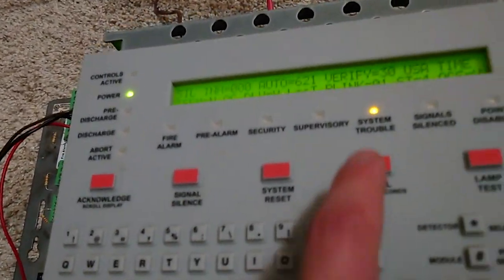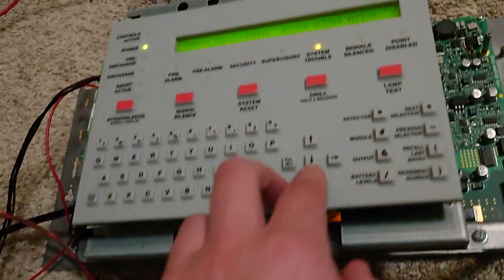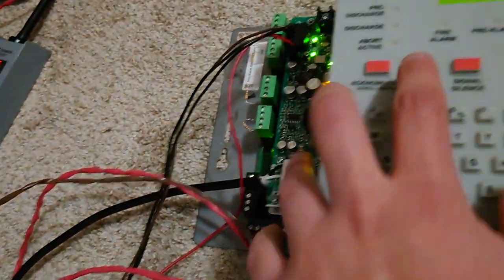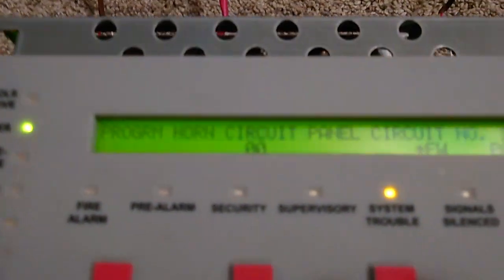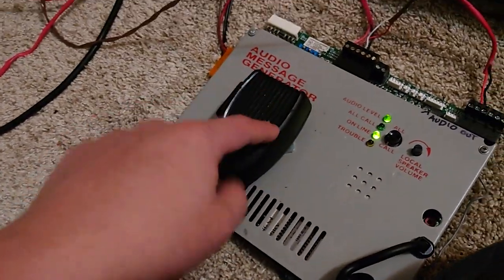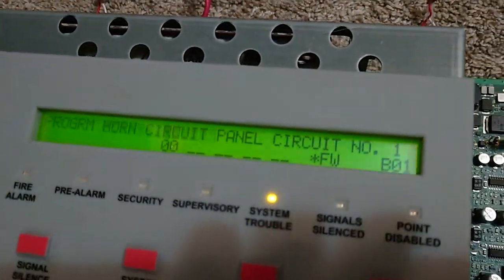So then you want to go into your panel programming. Let me do the definitely hard-to-guess default password. And then you want to go to System, ACSY, and you want to have your first annunciator — you've got to set that to A. The second one is also set to A. This is my preferred annunciator. And then you want to make sure that you have your NAC1 set to no coding and silenceable, because NAC1 controls this thing.